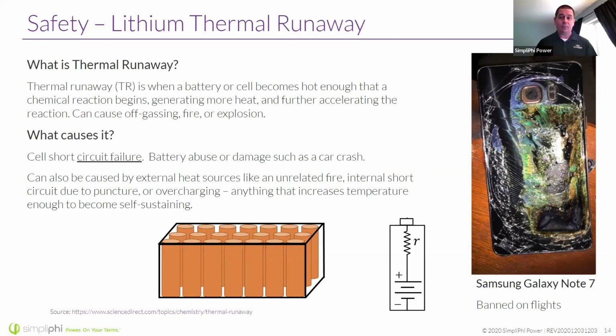Not a lot. So to Nathan's point, if you look up puncture tests for different lithium ion batteries, some of them can look like a firecracker or worse. There's fire, there's explosion, there's off-gassing, deflagration, which is basically flying pieces. For a lithium iron phosphate battery, when you put it through that same puncture test, there's a little bit of fizzle. You can see that it's been punctured and there's some off-gassing, but what's really not happening is the thermal event that starts to run away.